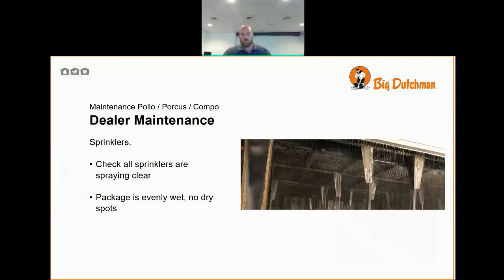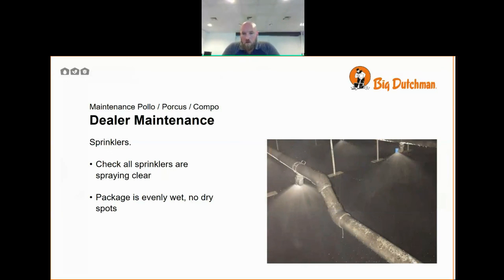What is your recommendation to check the sprayers, the sprinklers? Visually, you will be able to see very clearly when a sprinkler is blocked. It will either be dribbling like a tap that's halfway on, or it'll be stopped completely, or it'll have a really nice, beautiful cone-like spread. If it's got this nice clear cone spread, you know it's good. And if it's just spraying out of one side, you know there's something jammed in the other side. It's pretty clear when you go and look at them visually if they need attention. Oh, okay. And also check the underside of the package and any pre-sprinkling. You want to check the package for any dry spots and check the pre-sprinkling is all working correctly.